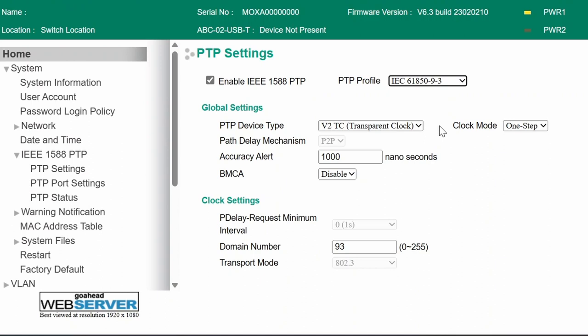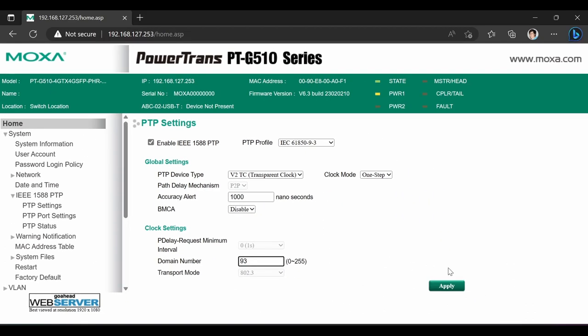Make sure that we are using peer-to-peer path delay mechanism, transparent clock role, and domain number 93. Once PTP settings are applied, I can proceed and enable PTP on the ports.